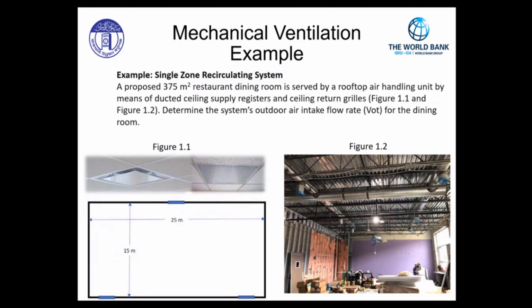Below the ceiling, figure 1.1 gives the dimensions of this particular dining room area: 15 meters by 25 meters. We're going to determine the system's outdoor air intake flow rate, which is V sub OT, for the dining room.